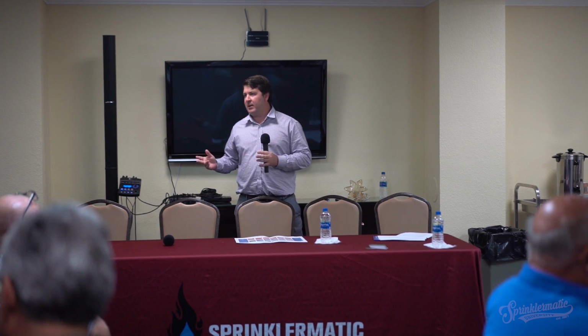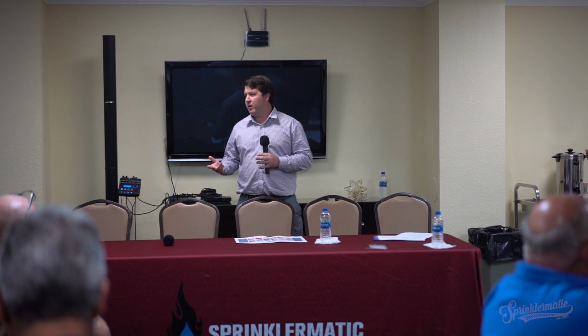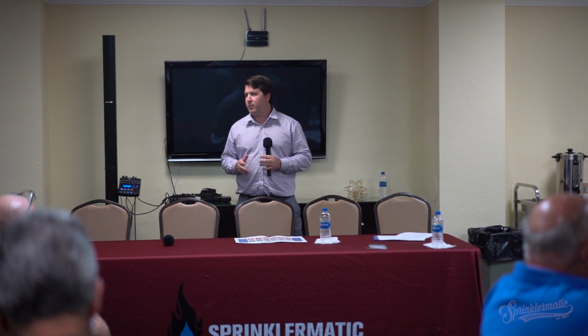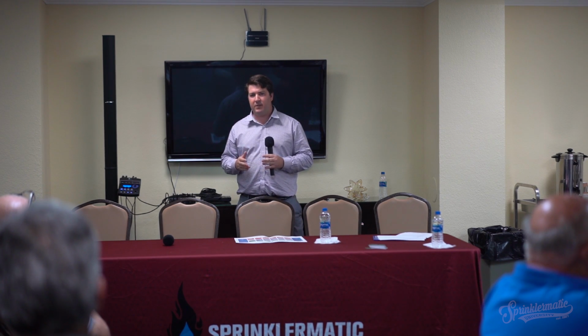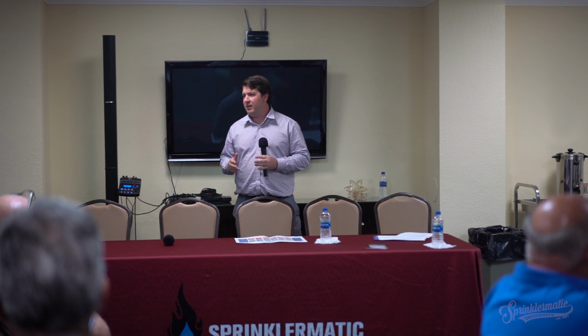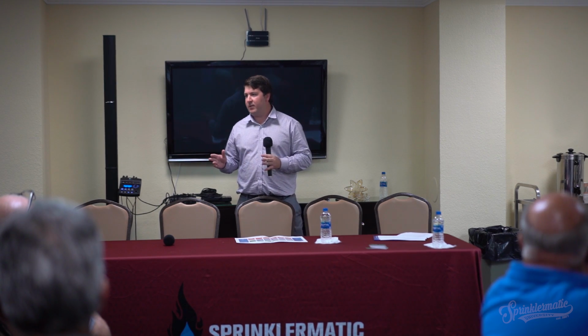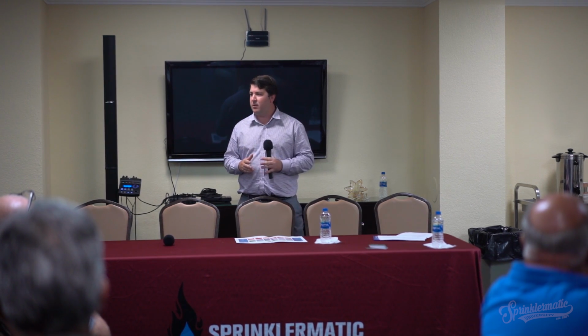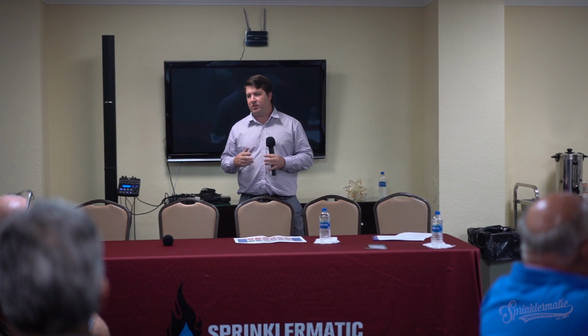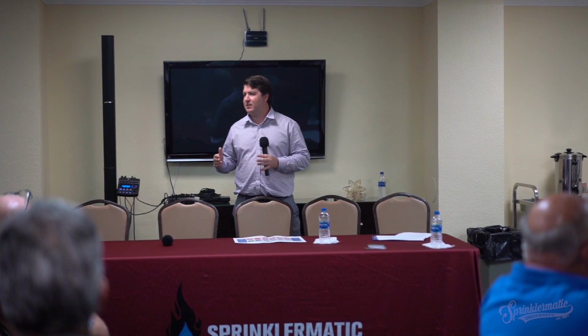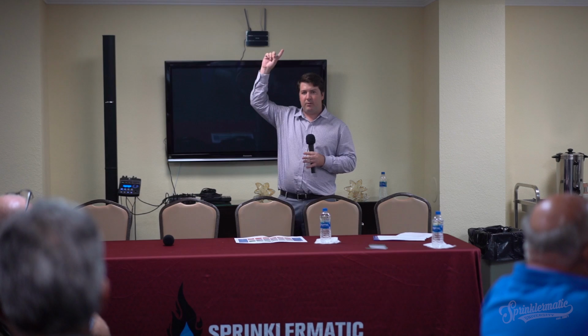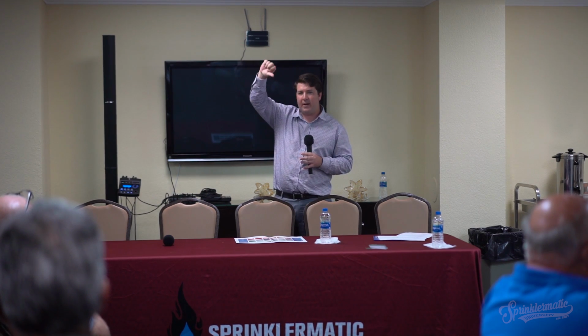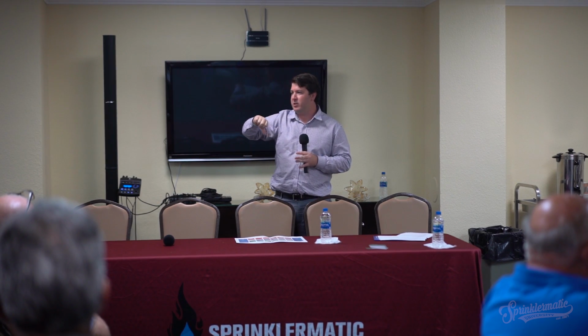So there was a federal mandate that went out, 20 states adopted, Florida being one, that says every high-rise in the state of Florida by the end of this year has to get tested for this emergency responder radio coverage. And if you pass, great, you have nothing to worry about. If you fail, you have to install what's called a BDA. It's a bidirectional amplifier, or a DAS, distributed antenna system. Pretty much an antenna on the roof that will talk to the fire department, then uses coaxial cable to distribute the coverage to the areas of low coverage.